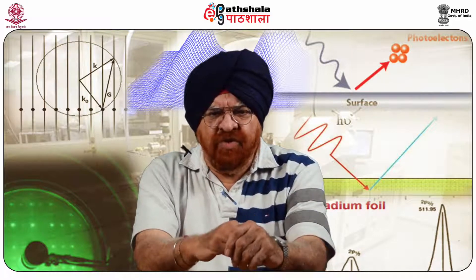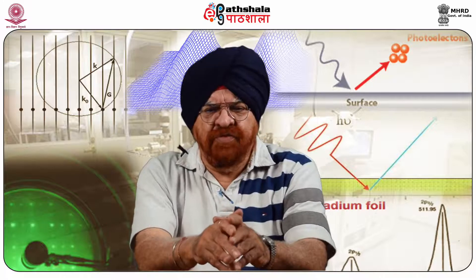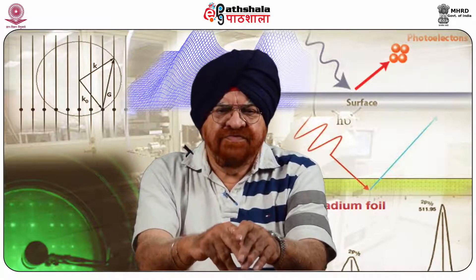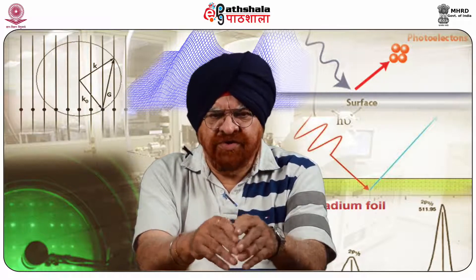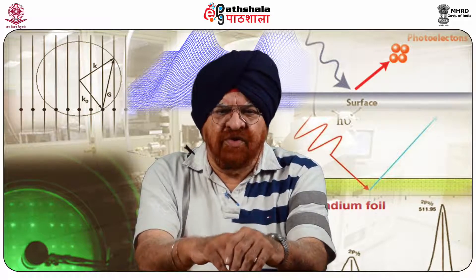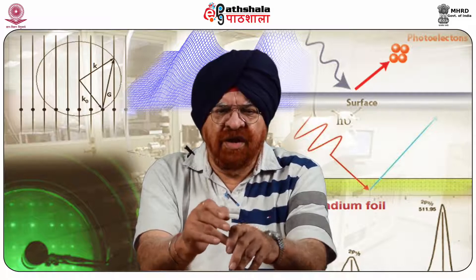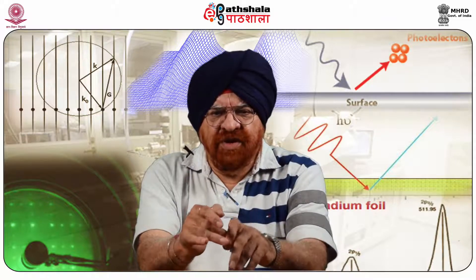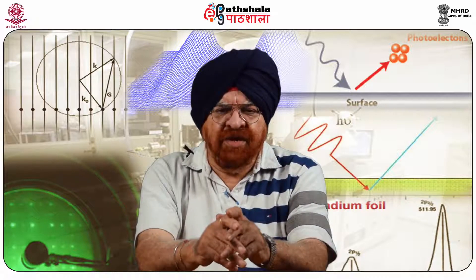KPFM is a scanning probe method where the potential offsets between a probe tip and a surface can be measured using the same principle as a microscopic Kelvin Probe. The cantilever in AFM is a reference electrode that forms a capacitor with the surface, over which it is scanned linearly at a constant separation.